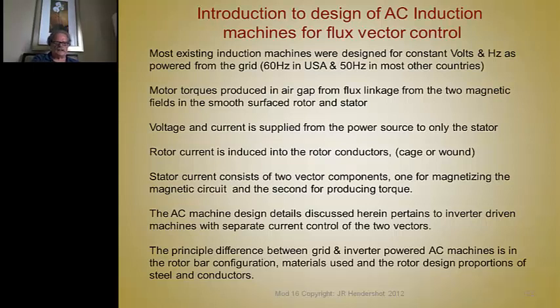So in summary, the principal difference between a grid and inverter-powered AC machines is the rotor bar configuration, how the rotor is made. The materials used for the steel core are about the same. You use steel for the rotor core and the stator core, the same electrical steels we use in all machines. Typically, small induction motors, maybe under 500 horsepower, are all aluminum die cast, and the ones that are larger than that have fabricated rotors because the die casting dies get too big, I guess. I don't know how big they die cast machines now. But if you can't die cast them, you have to fabricate them by hand. You have to have separate bars and end rings, and then you have to weld them or fuse them together somehow. And if you're going to do that, you can use copper rotors as well. Copper rotors are used in a wide number of machines. We'll just be discussing that.